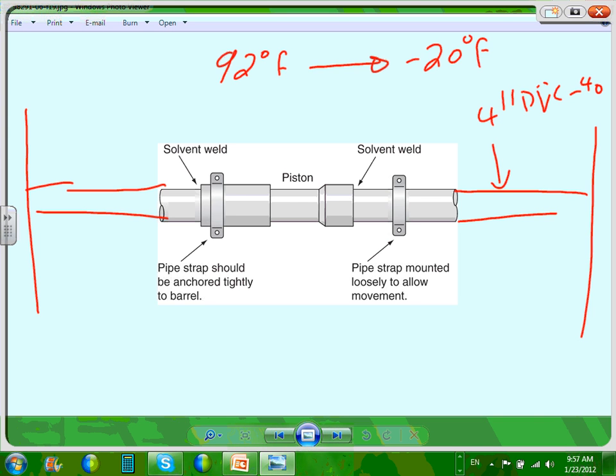So look at this. Do you guys agree with me? If you put a conduit in an environment where it's going to change from 92 Fahrenheit to minus 20, that will give you a temperature range of 112 degrees. Do you think the PVC is going to expand and contract? Most of the time, if you've ever been in that situation, you can find the conduit here and the box here, and in between there's a wire, because it contracted far enough that it moved away from the box. Be aware of this.